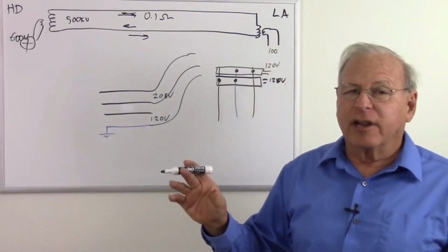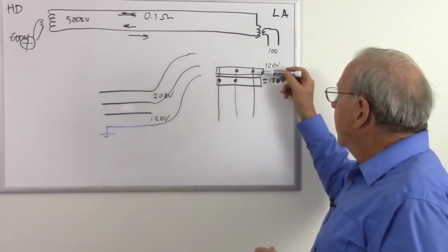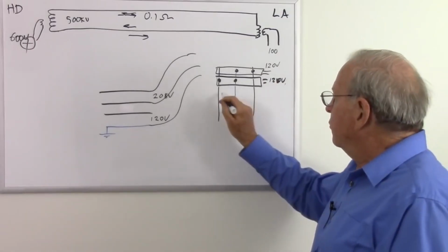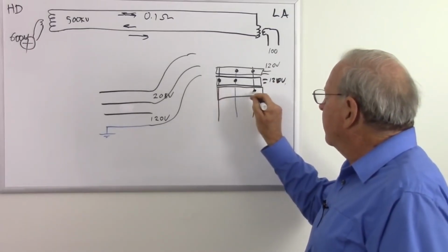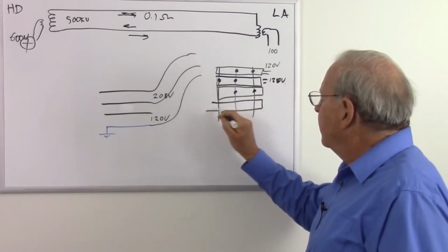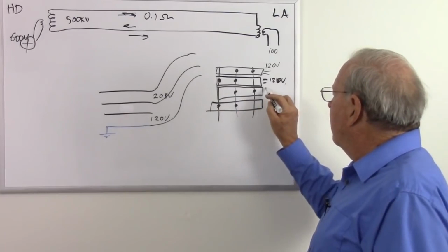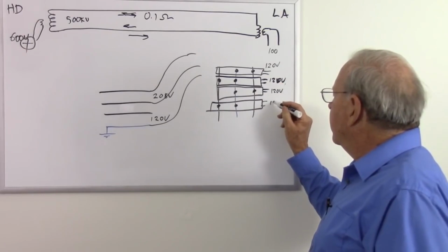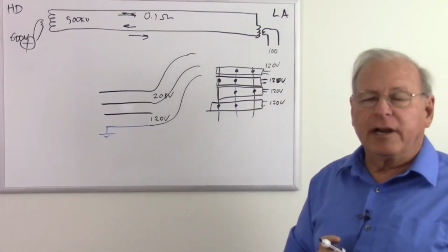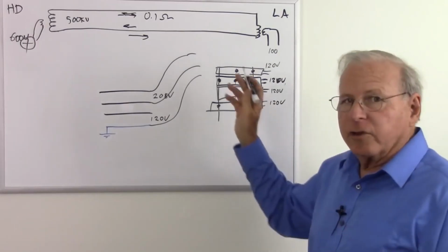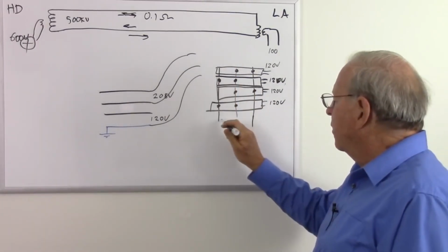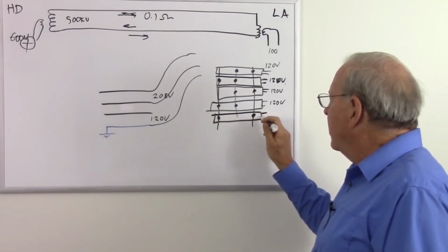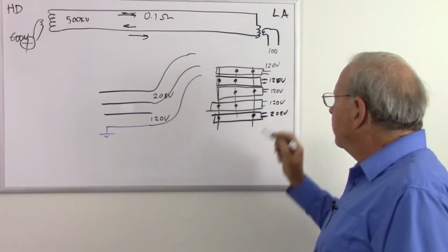So half of the sockets in a house and half of the light switches will be on one phase and neutral, and the other half would be on the other phase and neutral. So we put some more breakers in here. There's one connected there, put another breaker in here, and that one's connected to there and there. So they're all 120 volts. There's our wires coming out of them. 120, 120. So what do you do if you need an air conditioner or a clothes dryer or some other appliance that needs 240 volts? Well, they'll call it 240, but they simply take a breaker that's designed to go across two phases, and what do we get? 208 volts.